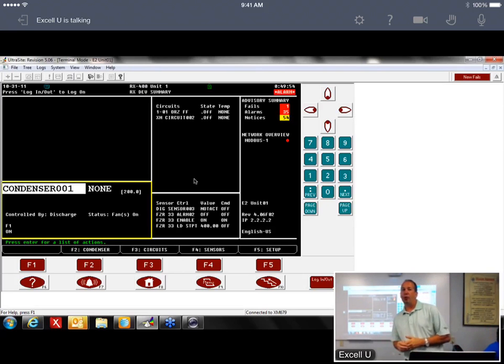The way a pulse valve works is it actually has an interval. A pulse valve is either open or closed, unlike a stepper valve, which has multiple positions and can be anywhere from 0 to 100% open. You're going to see a valve percentage and wonder, if I have a 50% valve percentage, how does that work with a valve that's either open or closed? The way that works is there's a time period that a pulse valve works. With this XM679 controller, that time period is 6 seconds.